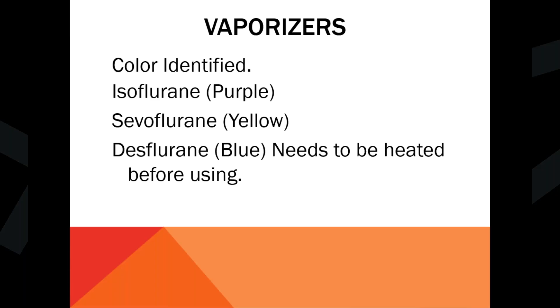One thing you can identify too, besides smell, is that each of the vaporizers has its own color code. The ones that we currently use: isoflurane's purple, Sevo's yellow, and desflurane is blue. One thing to know about desflurane is that it needs to be heated before use. It does come in a liquid, but it has to be at an operating temperature, and the desflurane vaporizer will not turn on until it's at its operational temperature. So you may get a call saying we can't turn on the desflurane. Well, that means they just turned on the machine. It probably takes 10, 15 minutes for the des to get up to operating temperature, but it won't let you turn on the volume setting on the top of it. So like I said, if you get any issues with des not coming on for you, then it's probably not up at its temperature.